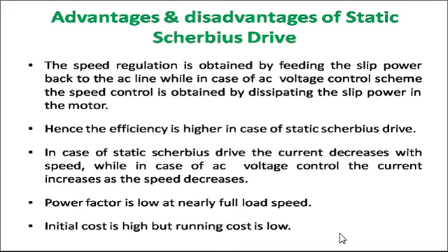Secondly, in case of the static Scherbius drive, the current decreases with speed, while in case of AC voltage control, the current increases as speed decreases. Then the power factor in this case is very low even for full load speed. For this type of drive, the initial cost is high, but the running cost is very low.